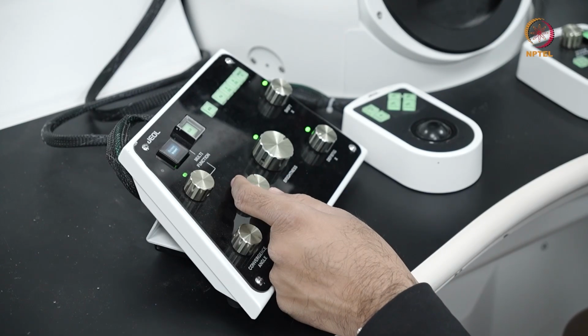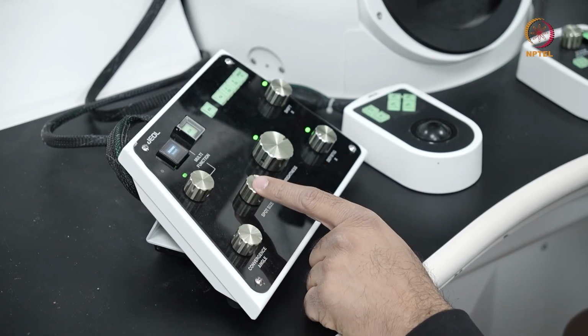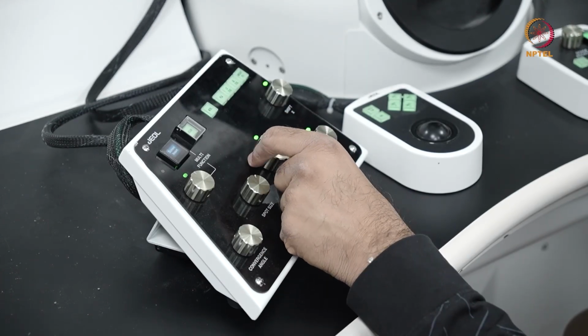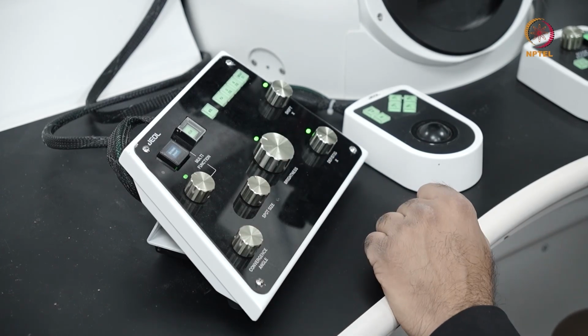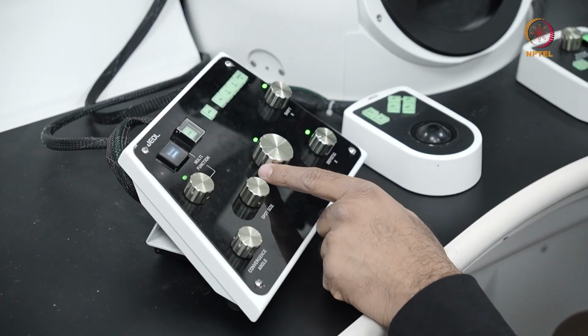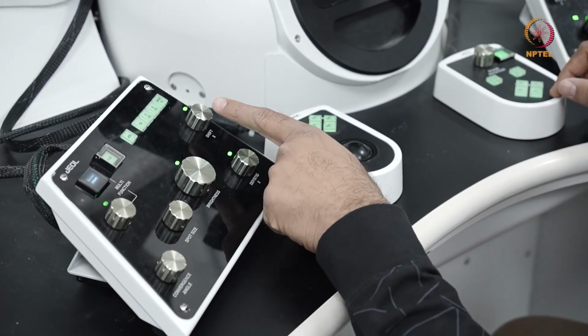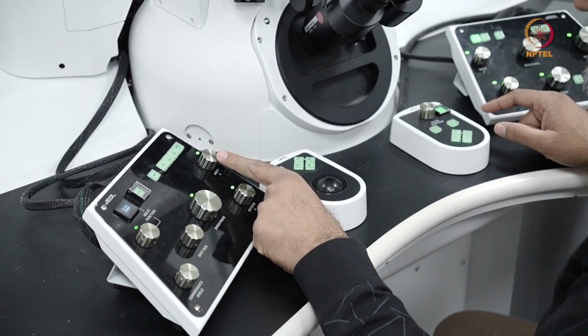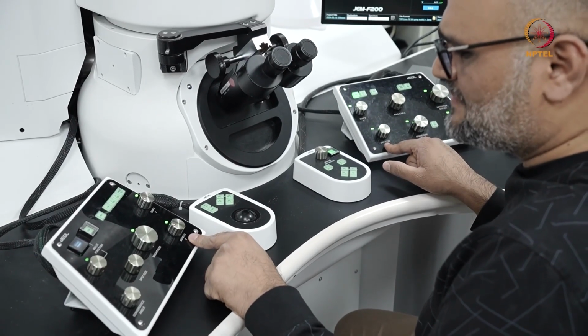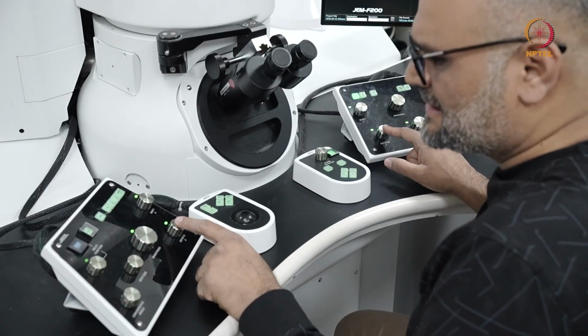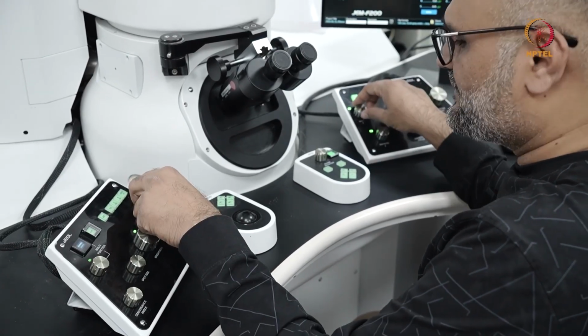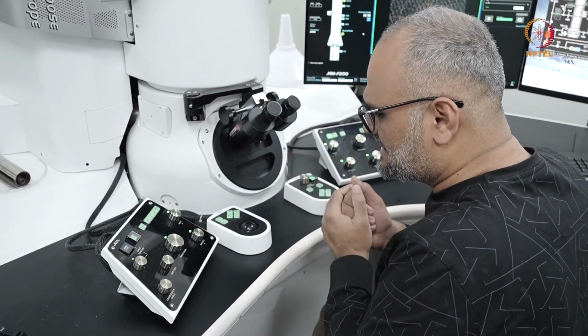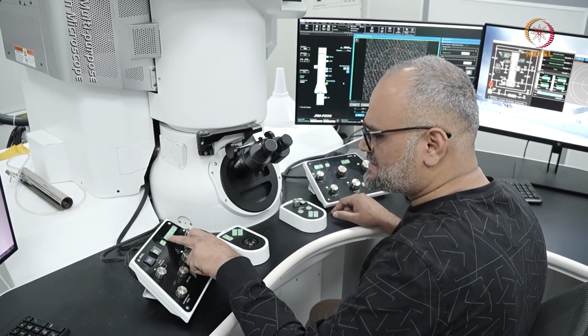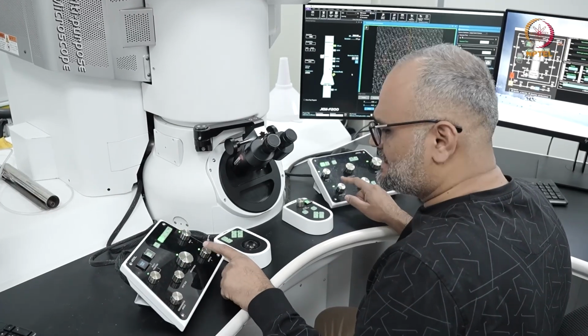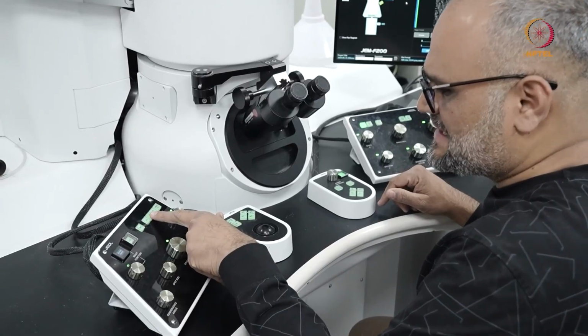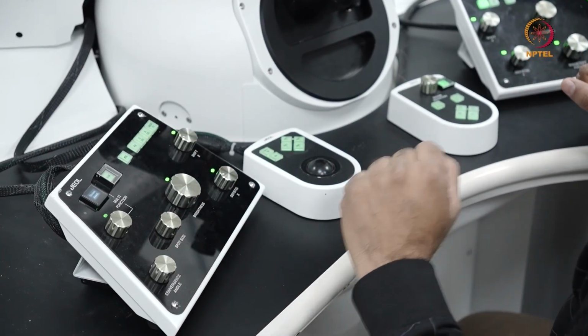The spot size you can vary from anywhere between 1 to 5 in TEM mode and 1 to 9 in STEM mode. The brightness that you see here is to adjust the intensity of the electron beam that is hitting your specimen surface. This is essentially controlling the strength of your condenser lens or the condenser mini lens. And the shift X or the shift Y here. So you have an equivalent knob on the other console and the deflection or stigmator knobs here. So these are analogous to the multifunction knobs you have in the Thermo Fisher microscope. So shift X and shift Y is to align the beam and to position the beam to the center of your screen. Deflection or stigmation, these knobs get activated once you select one of these options. For example, if I do PLA, then this is assigned to move the diffraction pattern, and if I have CL stig, I can correct for the condenser stigmation, and OL stig to correct for objective stigmation.